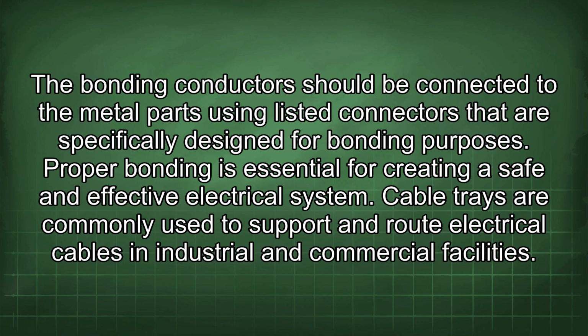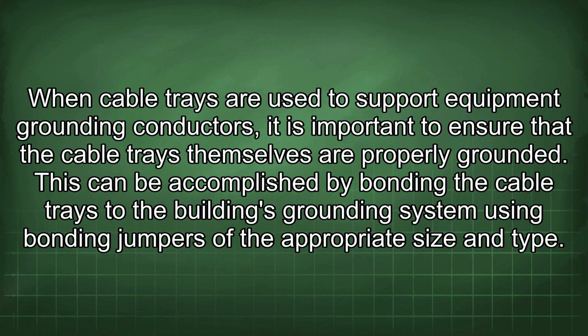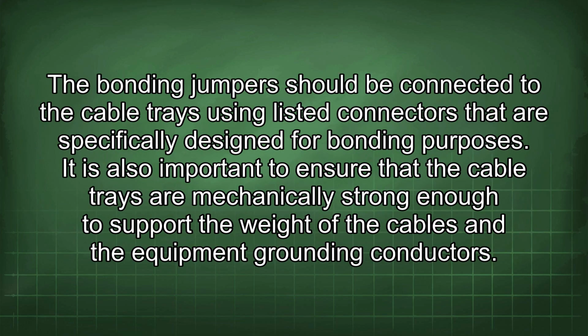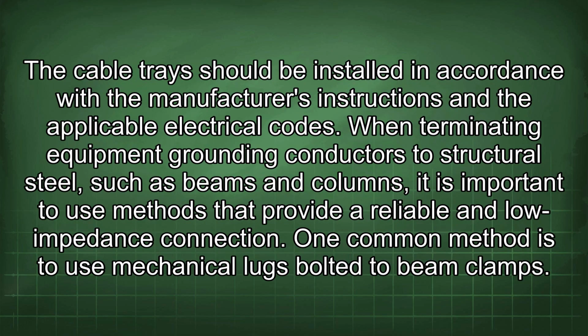Cable trays are commonly used to support and route electrical cables in industrial and commercial facilities. When cable trays are used to support equipment grounding conductors, it is important to ensure that the cable trays themselves are properly grounded. This can be accomplished by bonding the cable trays to the building's grounding system using bonding jumpers of the appropriate size and type. The bonding jumpers should be connected to the cable trays using listed connectors that are specifically designed for bonding purposes. It is also important to ensure that the cable trays are mechanically strong enough to support the weight of the cables and the equipment grounding conductors. The cable tray should be installed in accordance with the manufacturer's instructions and the applicable electrical codes.